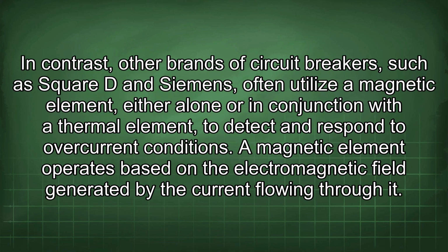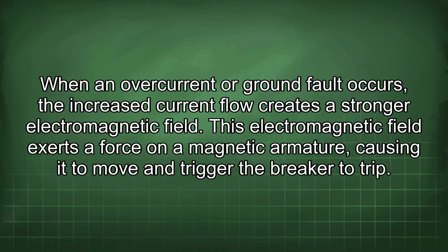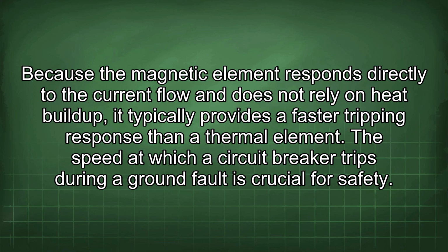In contrast, other brands of circuit breakers such as Square D and Siemens often utilize a magnetic element, either alone or in conjunction with a thermal element, to detect and respond to overcurrent conditions. A magnetic element operates based on the electromagnetic field generated by the current flowing through it. When an overcurrent or ground fault occurs, the increased current flow creates a stronger electromagnetic field. This electromagnetic field exerts a force on a magnetic armature, causing it to move and trigger the breaker to trip. Because the magnetic element responds directly to the current flow and does not rely on heat buildup, it typically provides a faster tripping response than a thermal element.